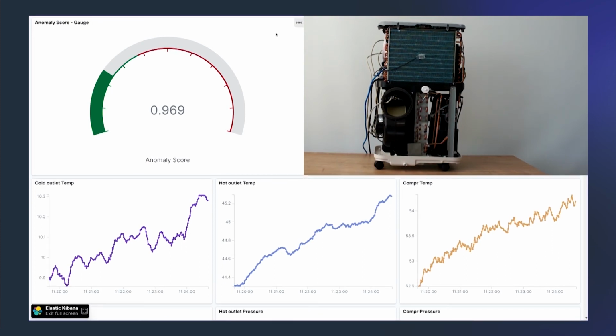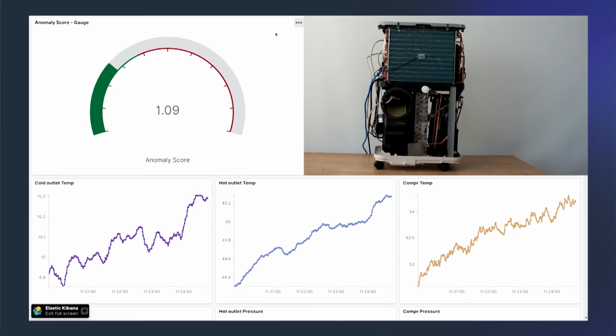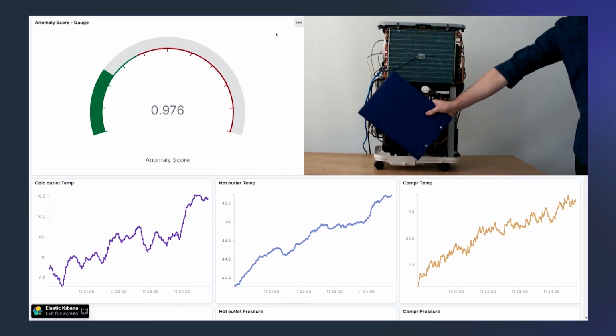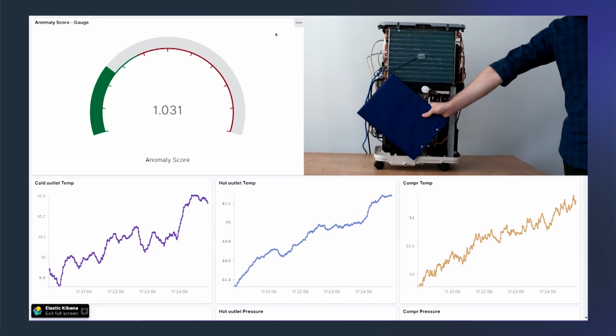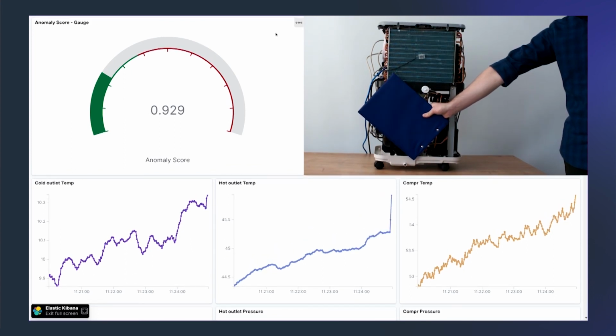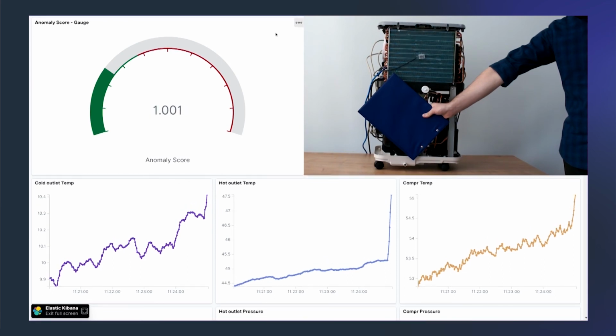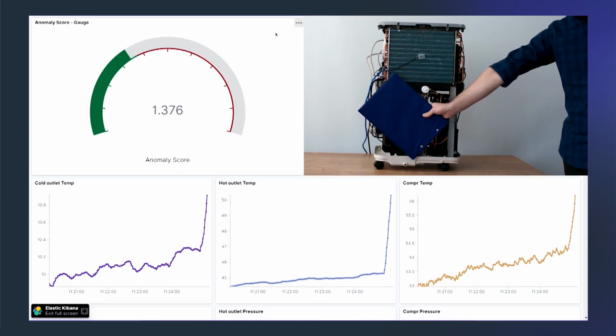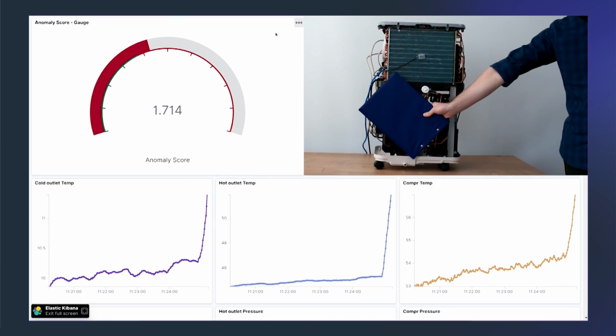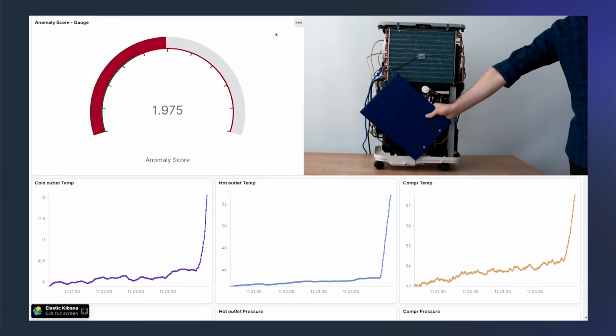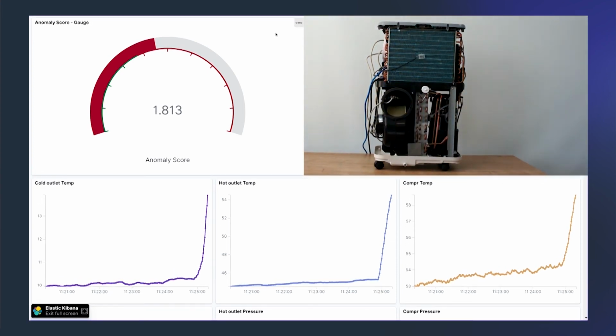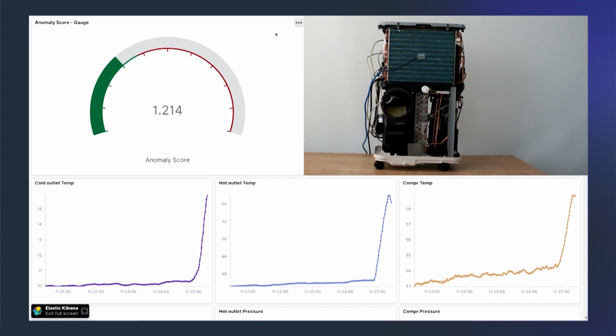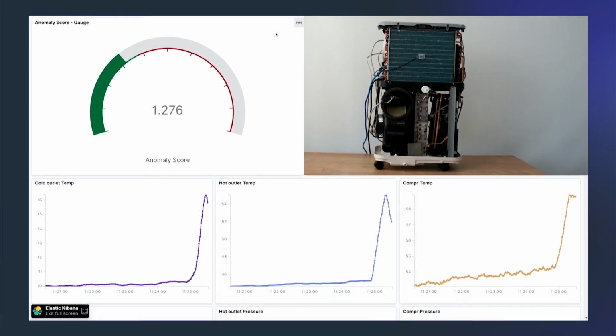Today we'll show you the compressor anomaly behavior and the fan anomaly behavior. We'll start with the fan anomaly behavior. As you can see, the system operates as expected, and we see a green zone in the anomaly score. Now we emulated a dirty filter and closed the fan with an obstacle. As you can see, almost in real time, the hot outlet temperature increases, and all the other temperatures also start increasing. And we see that an anomaly has been detected. So the anomaly score is in the red zone right now. A few seconds later, after we removed the obstacle, we'll see that the system will change its behavior and cool down a bit, and we'll see that now it operates as expected.